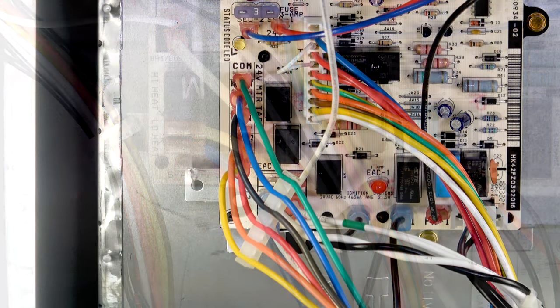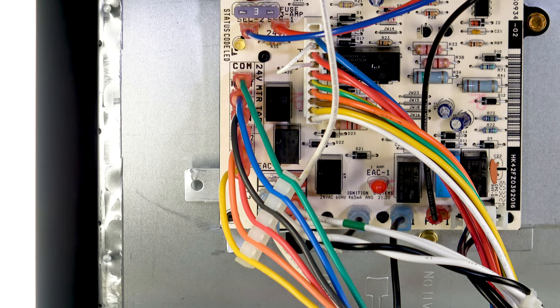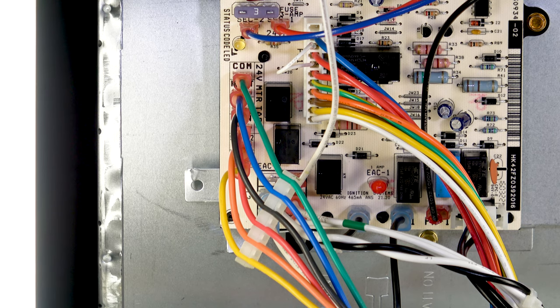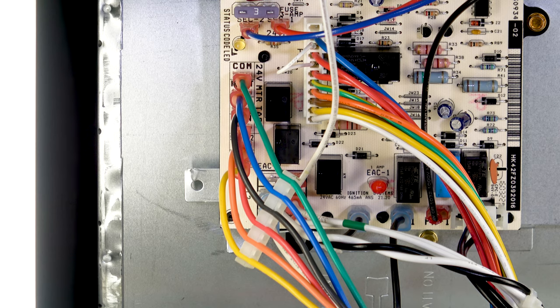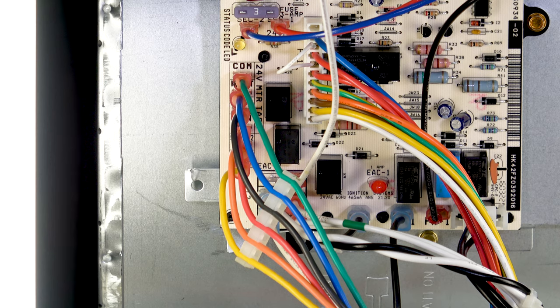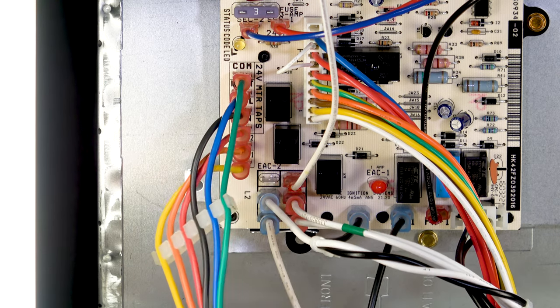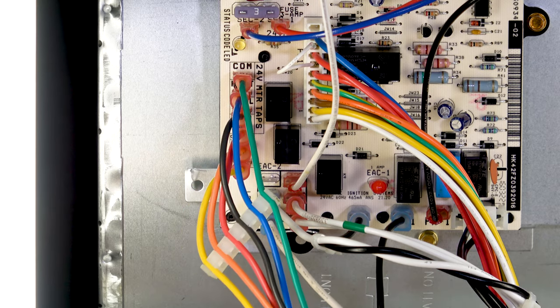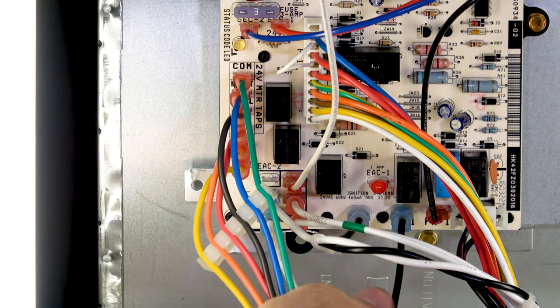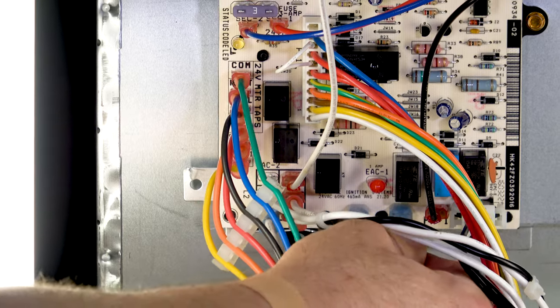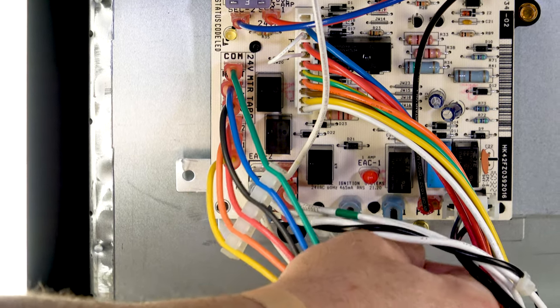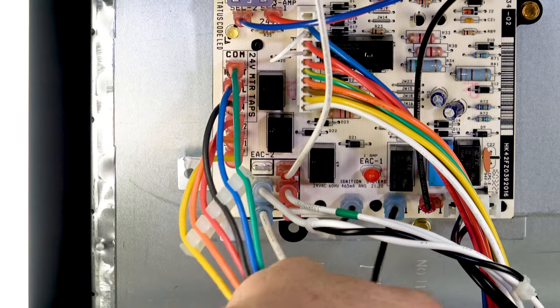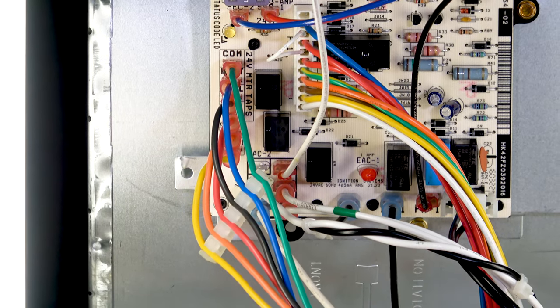Now we've moved on to a furnace with an ECM motor. The motor specifically in this unit is a non-variable ECM motor, usually called an x13 motor. This motor is run off 120 volts so your wires coming from the motor are going to be a black and a white. They're going to attach to the board and that's going to be your power going to the motor, your line voltage and your neutral wire.